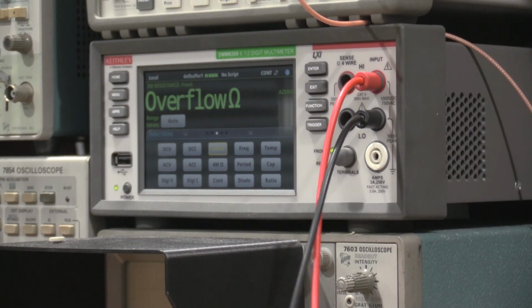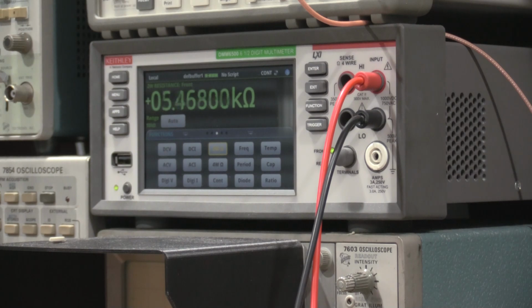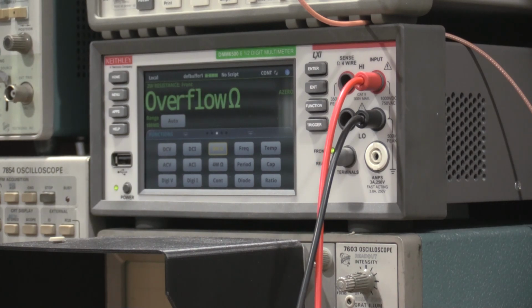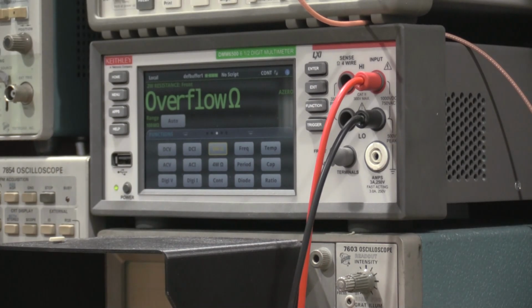We'll check section 2. It's dead already at this point, but we'll check it for good measure. This one's counting up, so that section may be healthy. And this one's counting up too, so that might be healthy, but this one definitely has a blown out section. So both of those caps were not healthy and needed to be changed.